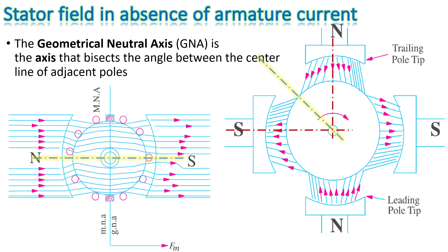The geometrical neutral axis is the axis that bisects the angle between the center line of adjacent poles. In a two-pole machine, the two poles have 180 degrees between them, so this angle is bisected by a vertical line — that is the geometrical neutral axis for this machine. In a four-pole machine, if we draw lines through the center of two adjacent poles, the angle between them is 90 degrees, so a line at 45 degrees bisects those center lines — that is the geometrical neutral axis for a four-pole machine.